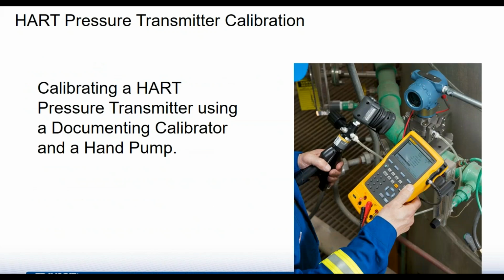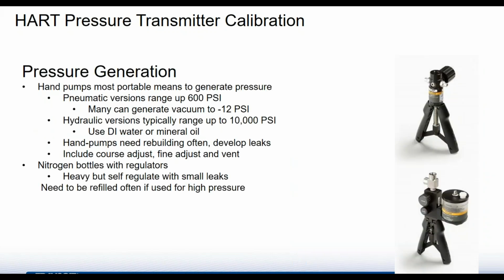So let's take a look at doing a calibration using a HART pressure transmitter and connecting up using a documenting calibrator and a hand pump. So first, you need something to apply pressure control to the device under test. A couple different options are using hand pumps, which can be pneumatic. Many of them go up to about 600 PSI. Some can also give you vacuum to do vacuum pressure calibrations.